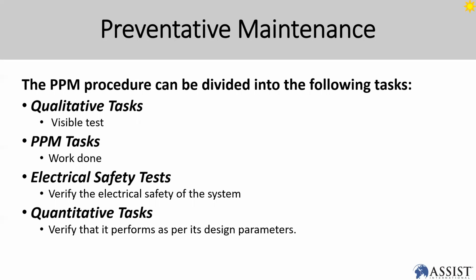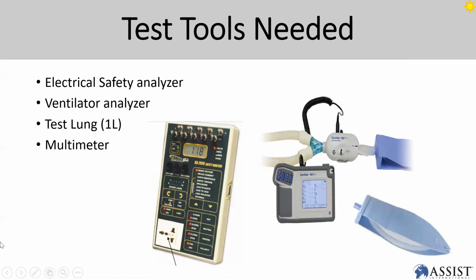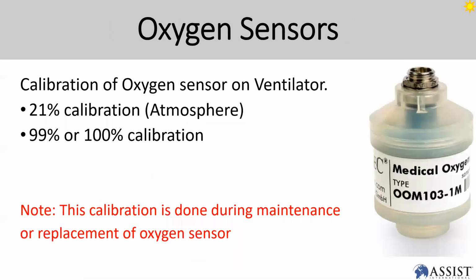So when you talk about PPM procedure, you're talking about visible tests. Basically, you're going to check the physical condition of the equipment, then documentation, all that. Electrical safety and quantitative tasks is basically you checking the performance of the device, whether it's working up to the right performance level. Test tools that you need, normally you need an electrical safety analyzer, ventilator analyzer, test lung, and multimeter. These are test tools that you always need to do your safety tests, all this.